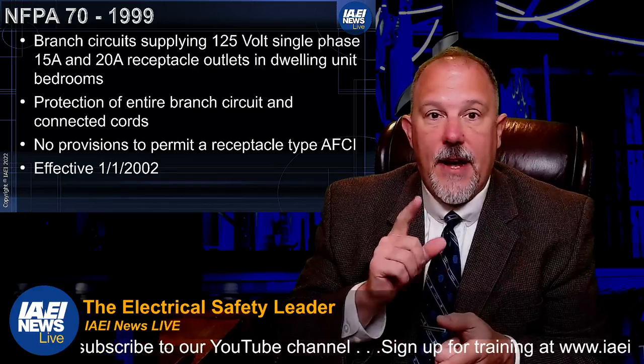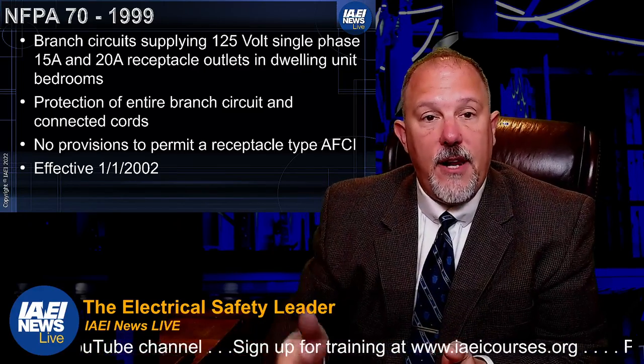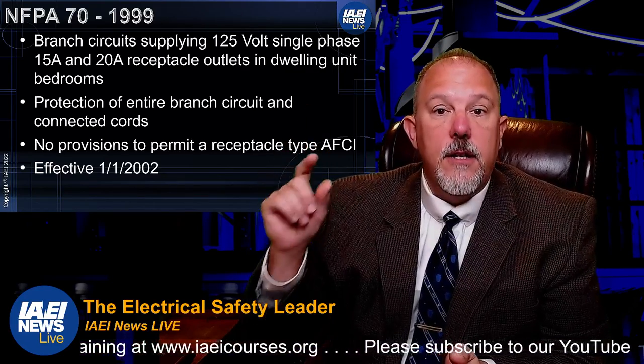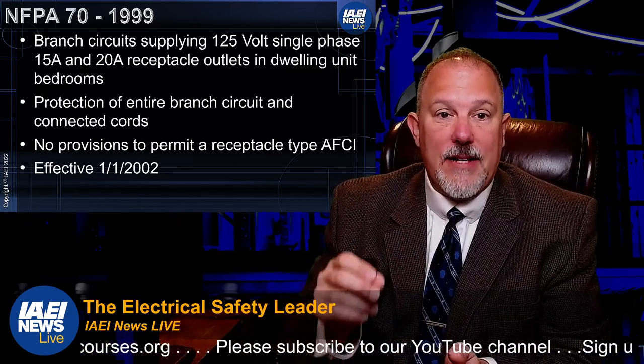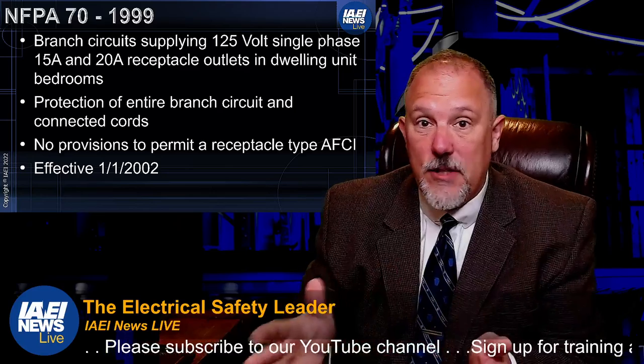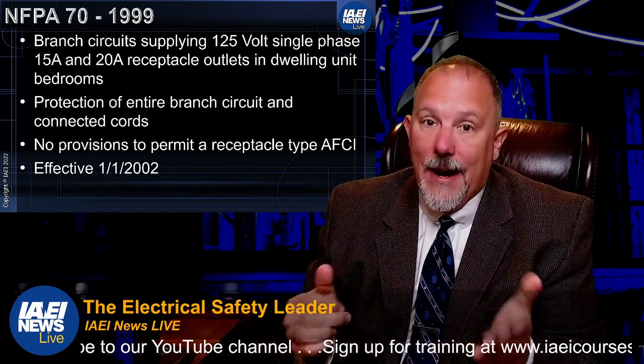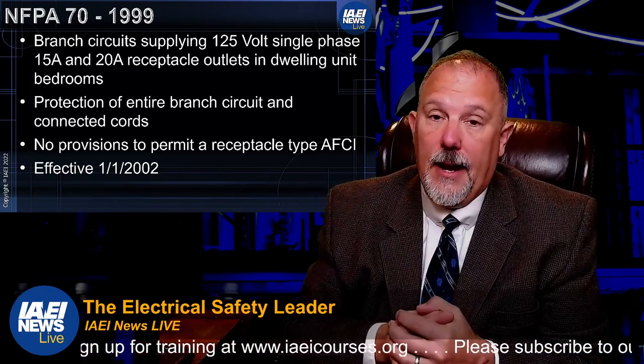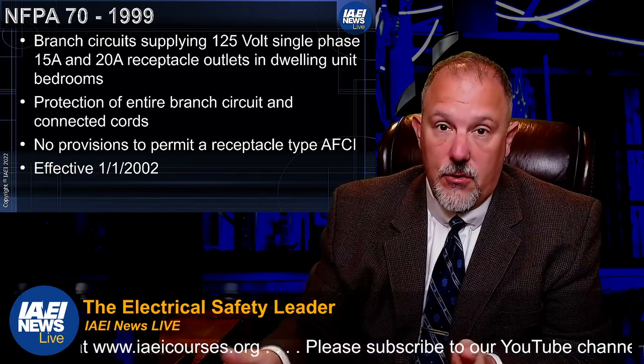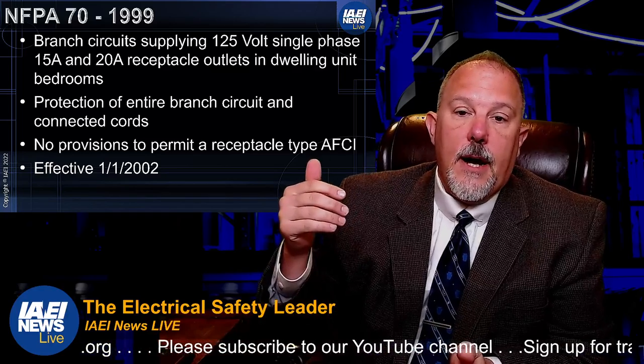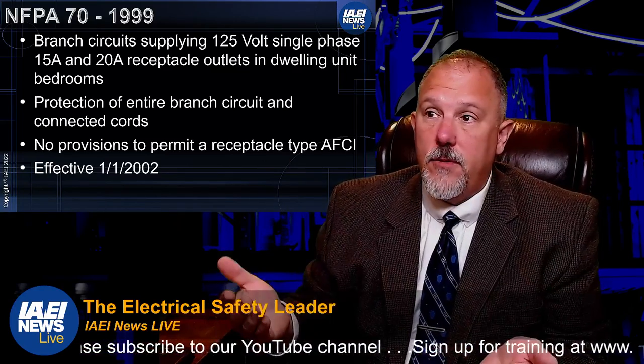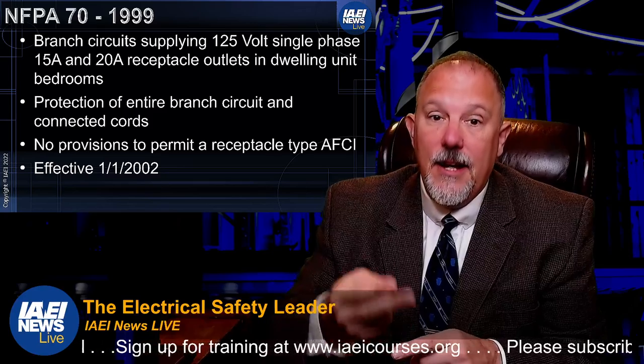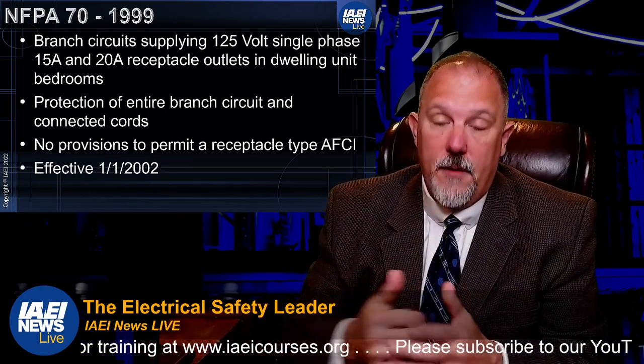AFCIs were introduced in NFPA 70 in 1999 to protect branch circuits supplying 125-volt, single-phase, 15- to 20-amp receptacle outlets in dwelling unit bedrooms, with an effective date of January 1st, 2002. That delay was given because only two manufacturers were on the market with an AFCI product — both making branch feeder type devices — and the industry needed more time to bring solutions.